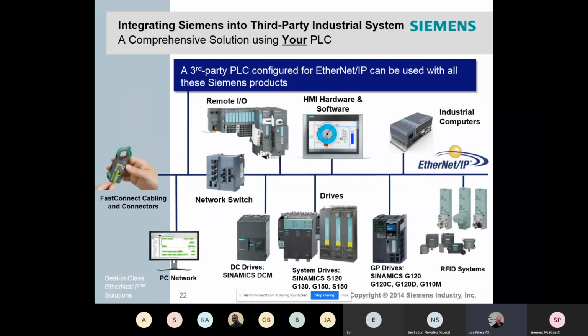Siemens has a comprehensive line of products with flexibility to communicate with Rockwell controllers and integrate into the Ethernet IP networks. From networking switches, distributed I/O, HMI hardware and software, RFID, drives to cabling, Siemens can communicate with the entire system. We will demonstrate this during the first part of today's webinar. Our products communicate with Rockwell ControlLogix PLC over Ethernet IP protocol.